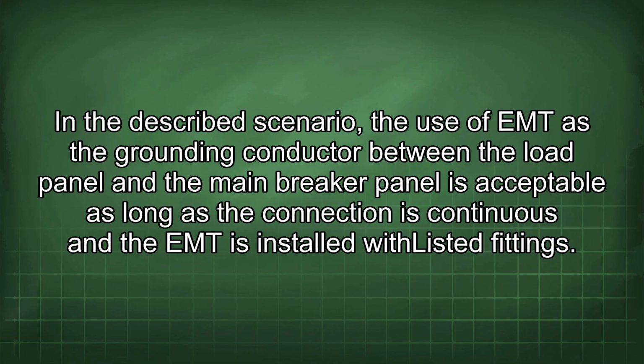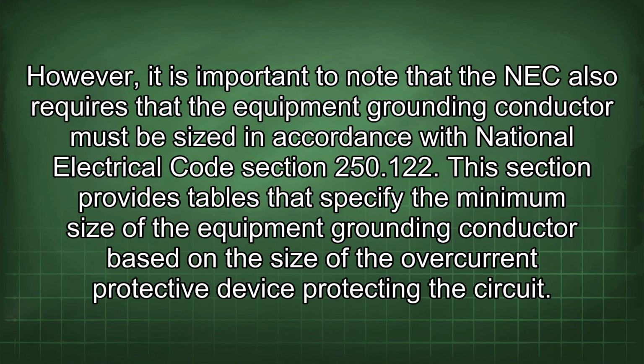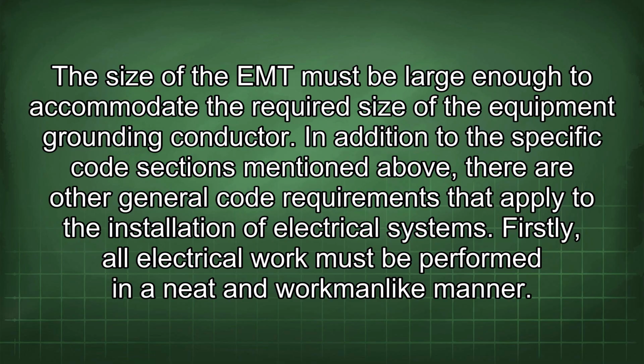In the described scenario, the use of EMT as the grounding conductor between the load panel and the main breaker panel is acceptable as long as the connection is continuous and the EMT is installed with listed fittings. However, it is important to note that the NEC also requires that the equipment grounding conductor must be sized in accordance with National Electrical Code Section 250.122. This section provides tables that specify the minimum size of the equipment grounding conductor based on the size of the overcurrent protective device protecting this circuit. The size of the EMT must be large enough to accommodate the required size of the equipment grounding conductor.